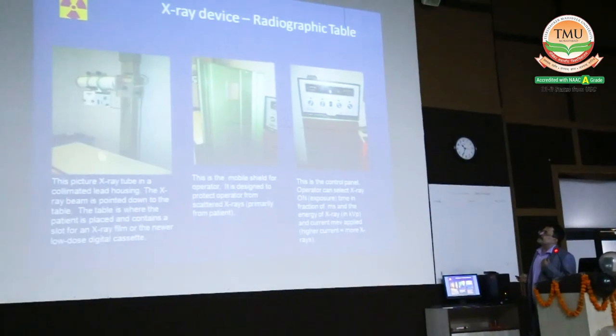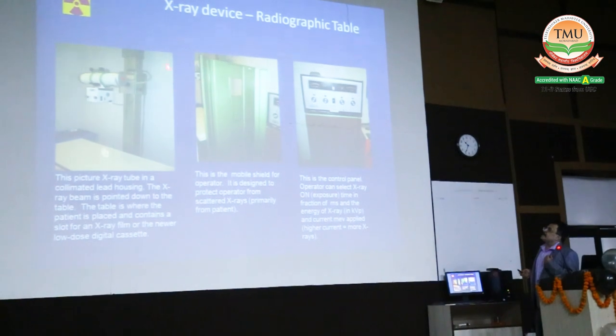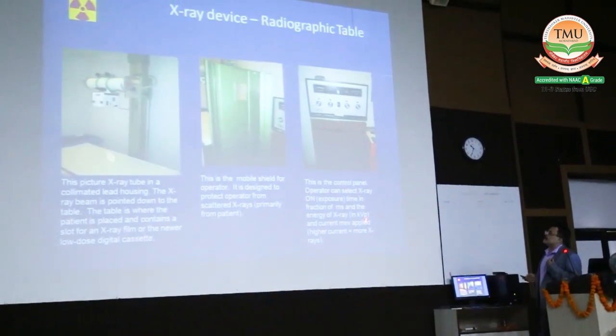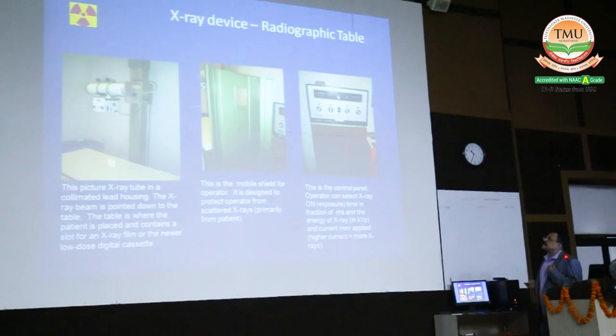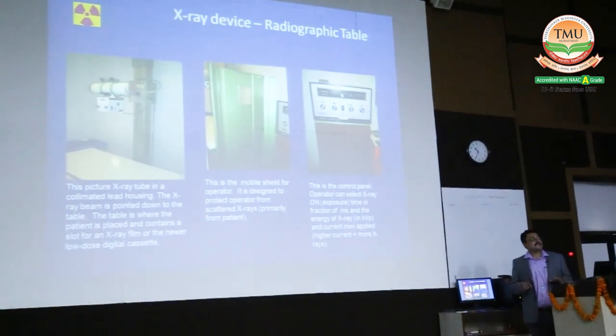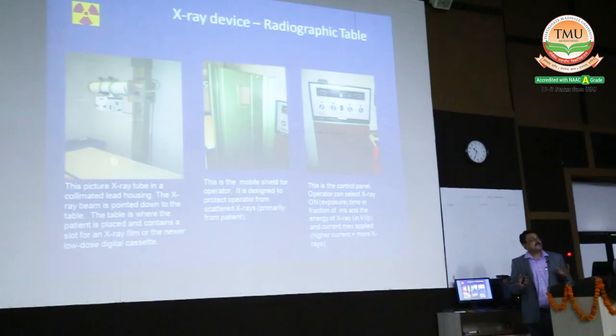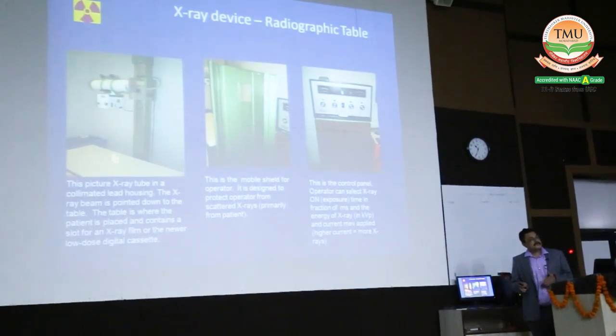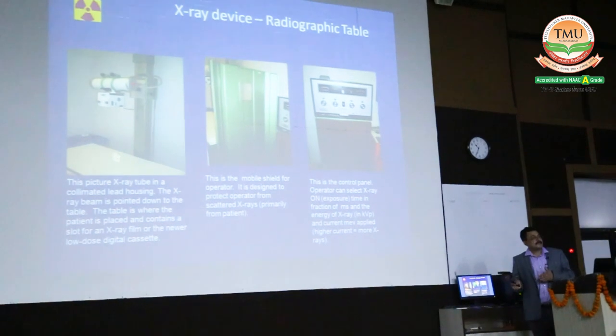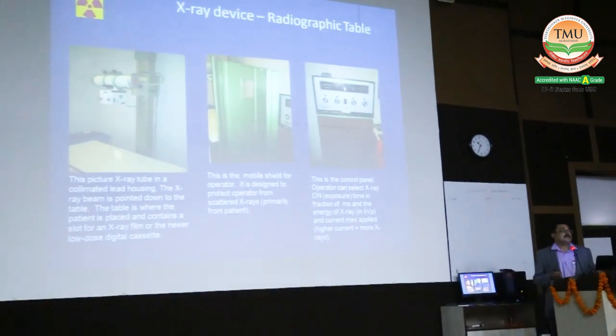These are the predominant sources of radiation. The conventional X-ray unit has a mobile shield for operators and a control panel. Technicians should keep in mind that the control panel is basically used to control the potential difference applied to the cathode and anode, and you have to be very cautious about the milliampere settings.